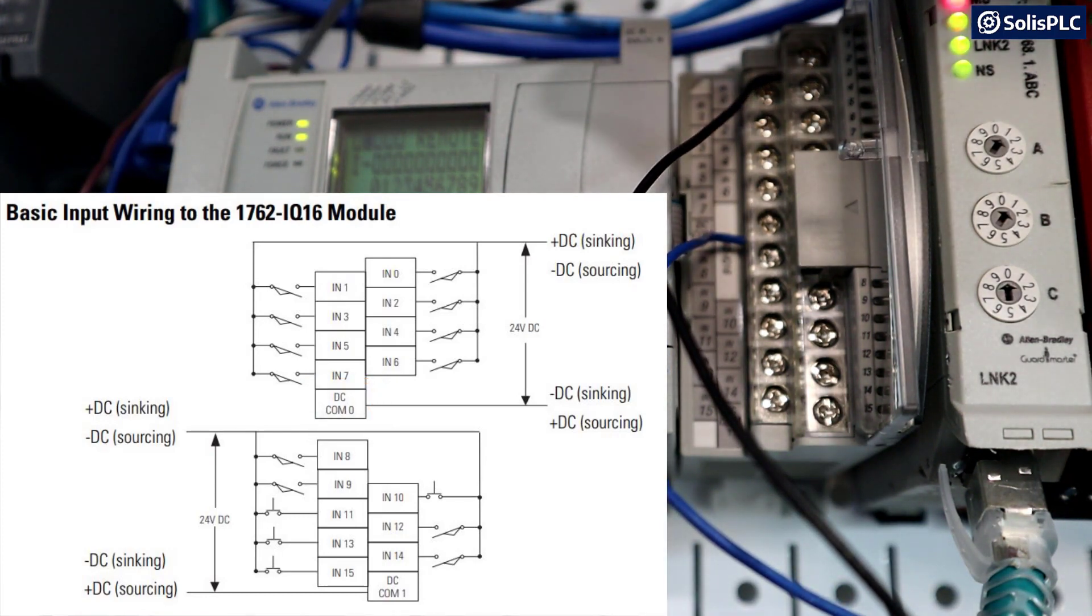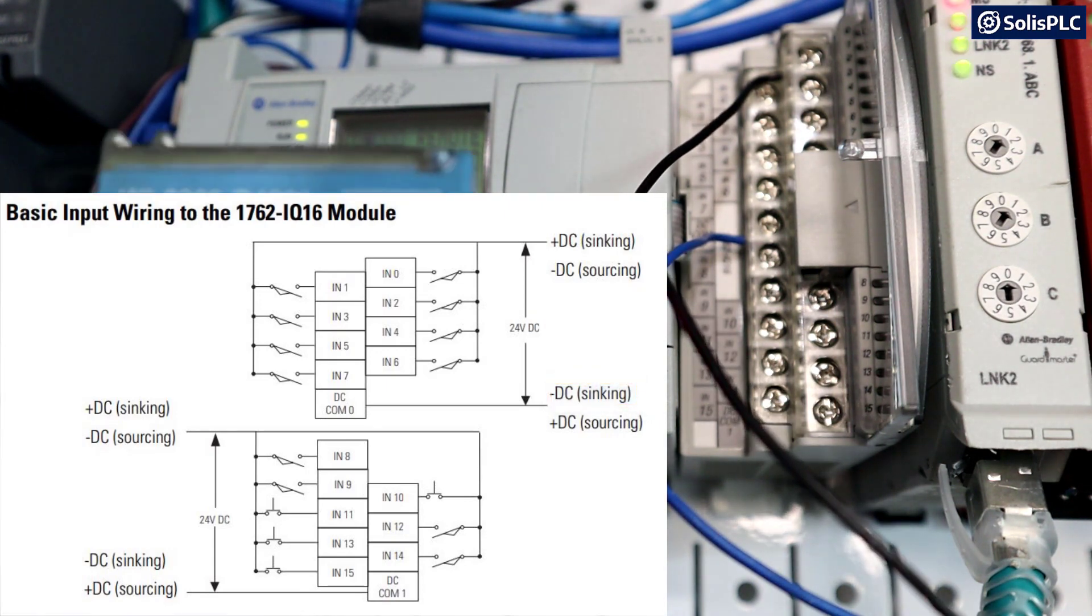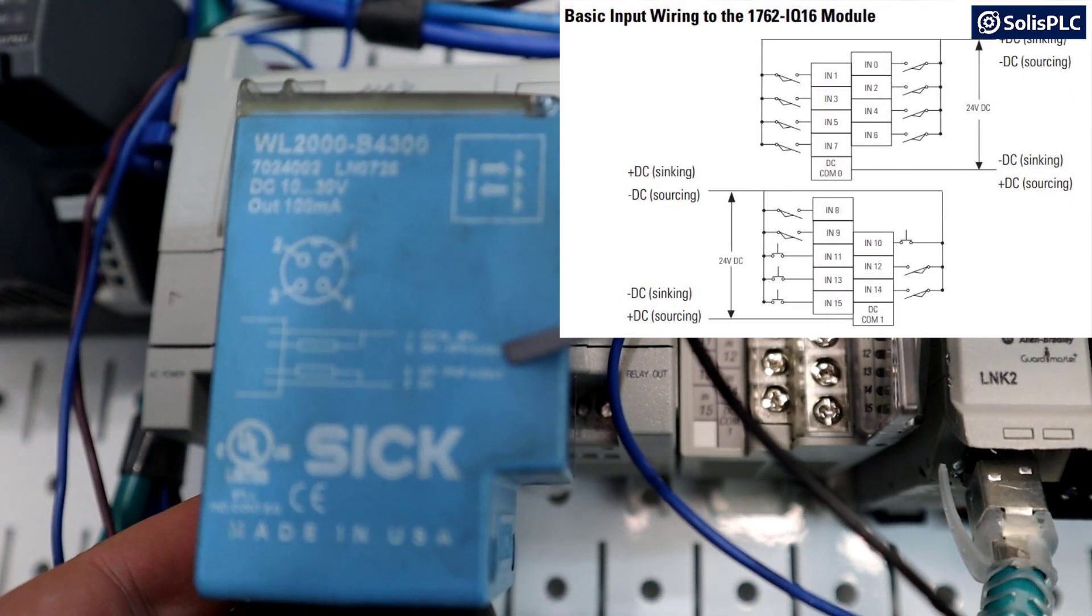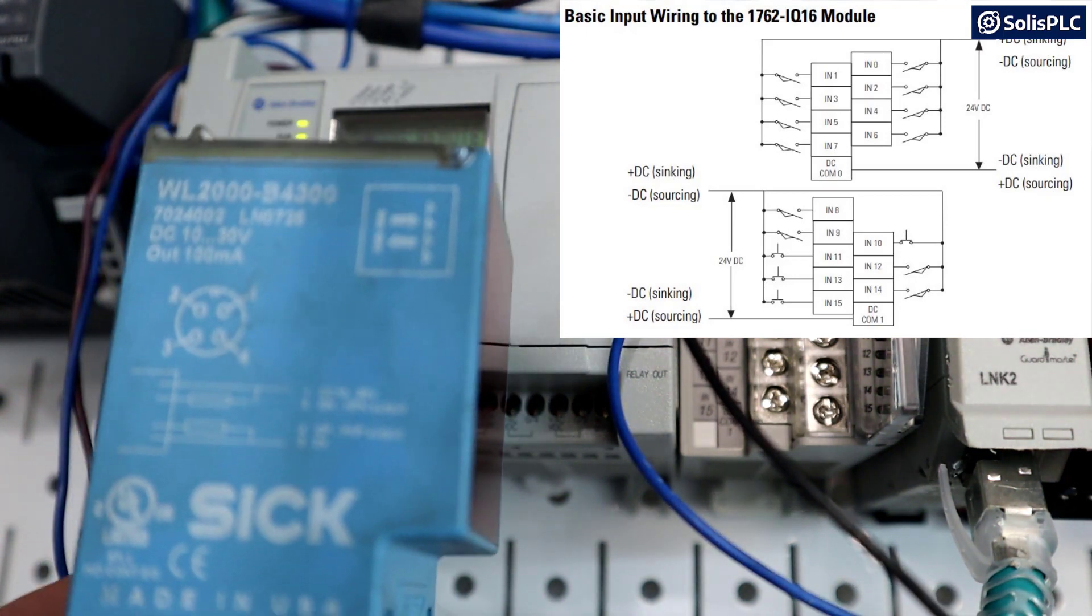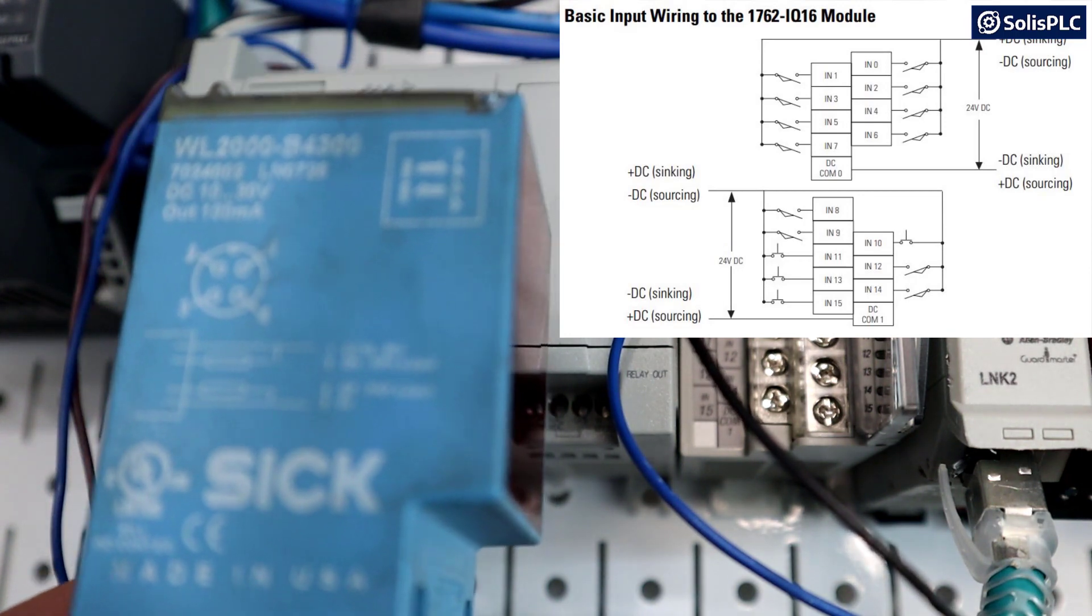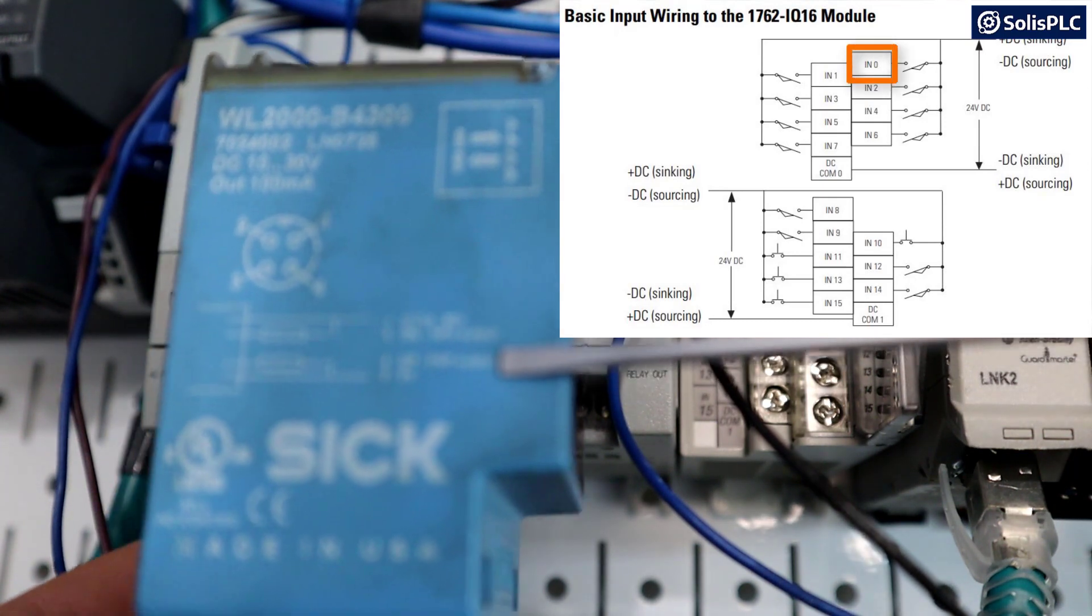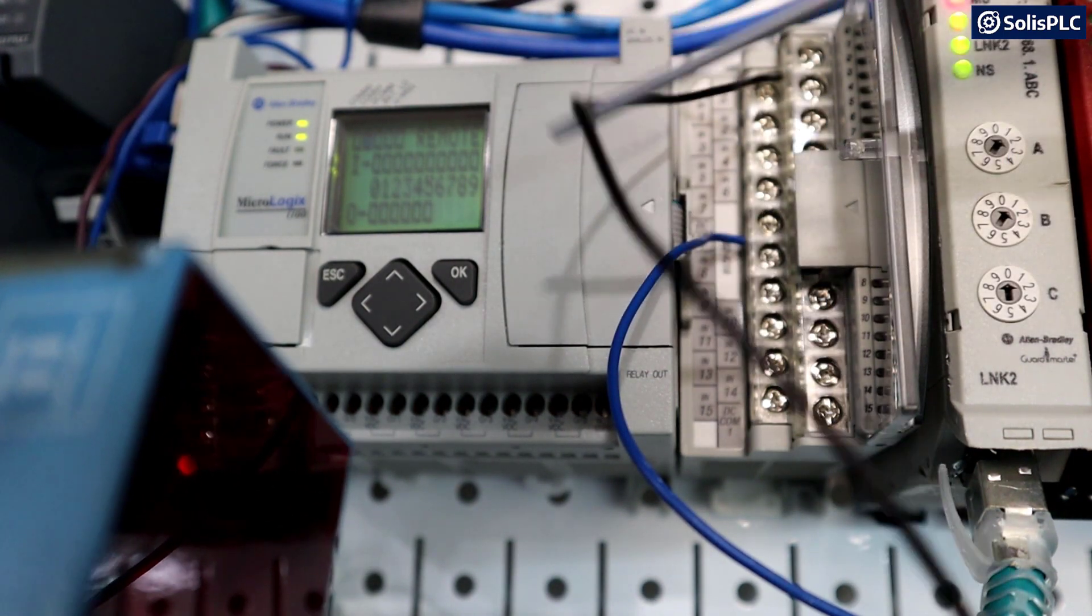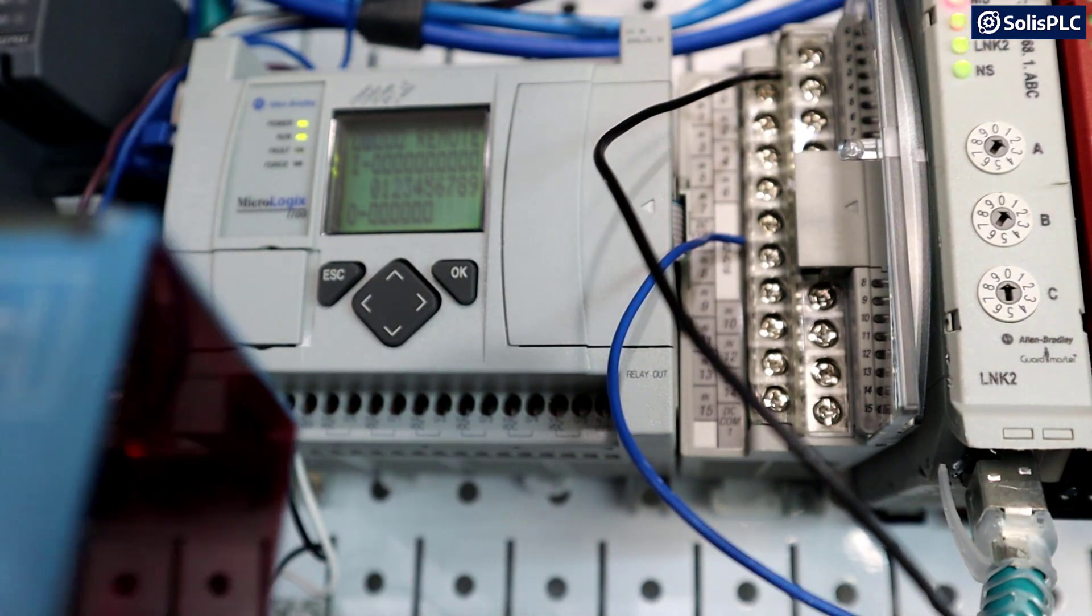The common wire is going to be landed on this terminal over here, you'll have a schematic as well. So this is the fifth on the left side from the top, and it has been placed on the digital voltage ground, the DC minus here on the top of the MicroLogix. Then for the sensor, the reason for that is if we pull this into our frame, you'll notice that we've got two outputs. One is the NPN and the other one is the PNP. The conventional standard in the North American region, at least, is to have sinking inputs. And for a sinking input, we need a PNP output on the sensor side. So that's going to be wire number four, which is the black cable that has currently landed on input number zero. And that's going to be the signal coming back from our sensor.